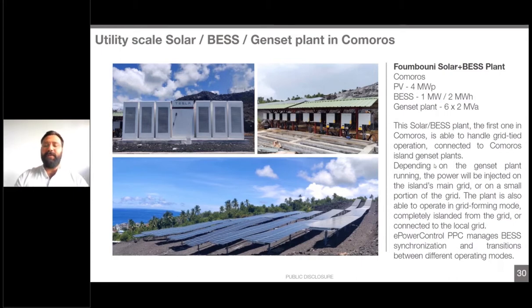We used in this project our PPC controller, where there were some specific requirements to switch and island the BSS and the PV system. In that case, the controller was able to switch from the genset to the BSS as the grid forming unit on site. And by that, for sure, we increased the solar penetration and prioritized the use of renewable energies.